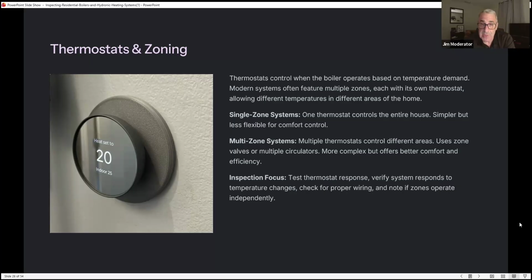The listing agent shows up and says, you guys don't know what you're doing. I'm going to put it on fan. And the system starts blowing air. I said, that's great. You're moving air, but you're not moving heat. And why would somebody not replace a 38-year-old unit and put something brand new as an air handler right on top of it? So all the people who installed it, probably last week, screwed up the heating system. So you want to test and make sure everything works from every thermostat, if possible.